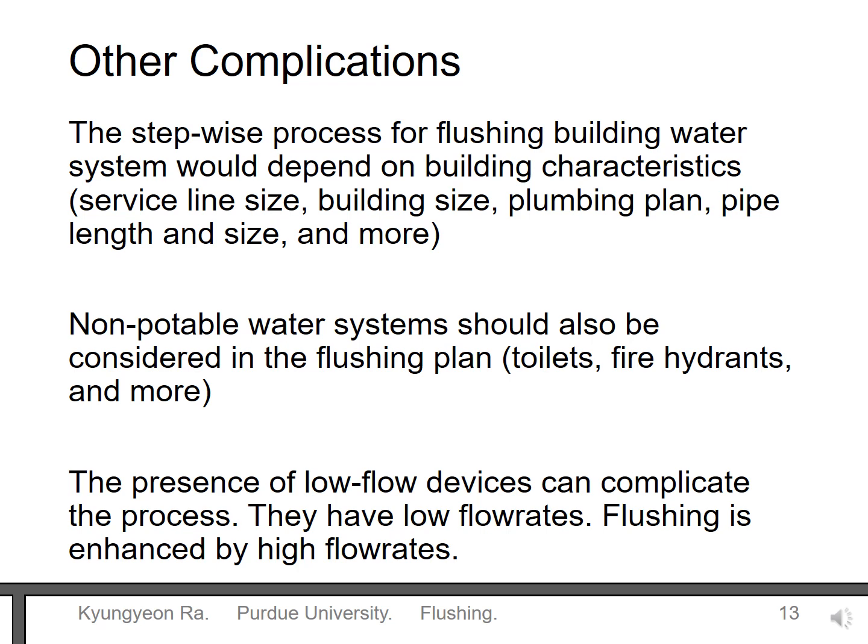There are some other complications that need to be considered. It is important to know all the water systems in the building because everything affects water movement. So you need to make sure to flush dead ends and include non-potable water systems like toilets and fire hydrants. If there are low-flow devices like water bubblers flowing really slowly, you may need to flush for a longer time or even swap the point-of-use device as well.